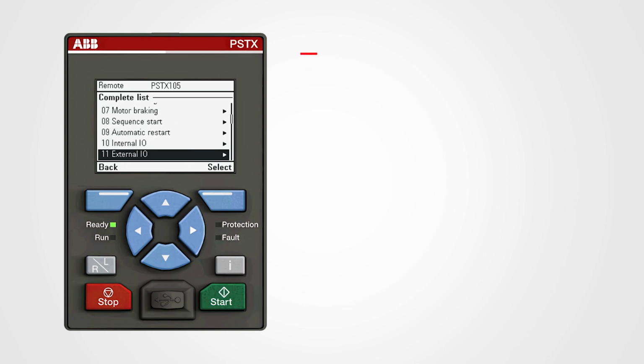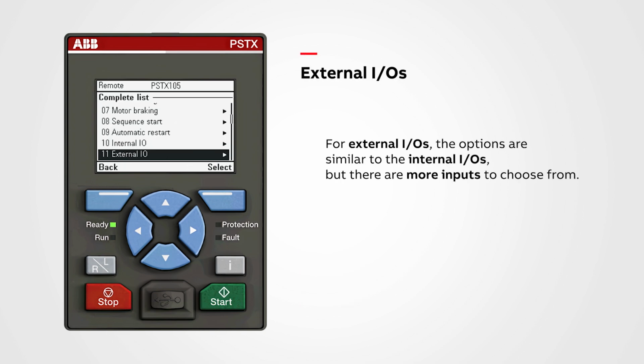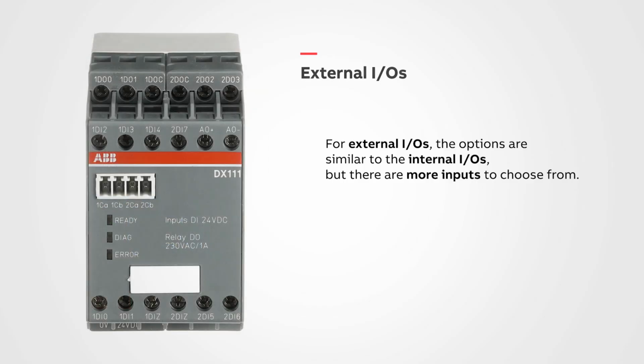For external IOs, the options are similar to the internal IOs, but there are more inputs to choose from. An extension I/O module is required if external IOs are to be used. For instance, the DX111 I/O module is an example. Take a look at the product photo.